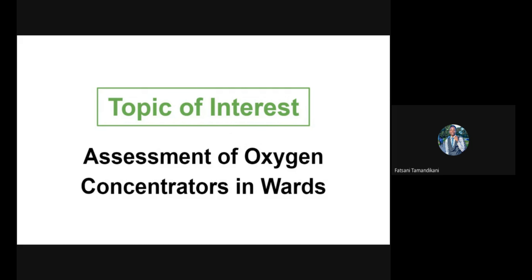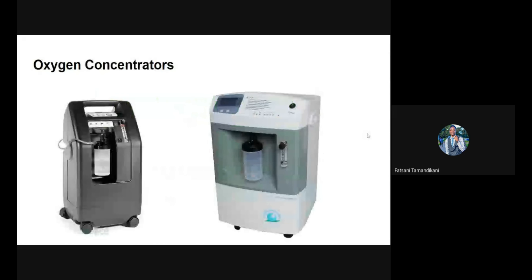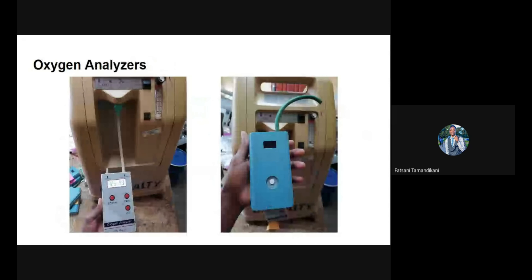Some oxygen analyzers also have a pressure sensor for checking oxygen delivery pressure. For a successful purity assessment, first turn on the concentrator and let it run for at least five minutes before connecting the analyzer to the output. The reason for waiting is that the product tank may have stored oxygen from last use, and we want purity and pressure to stabilize in the product tank. We also want to avoid measuring during startup voltage surges or drops due to power quality issues.